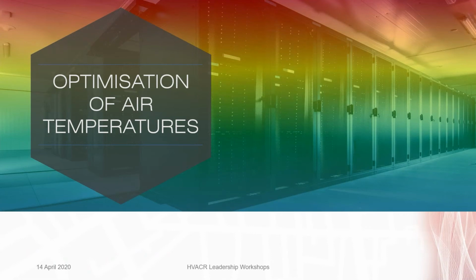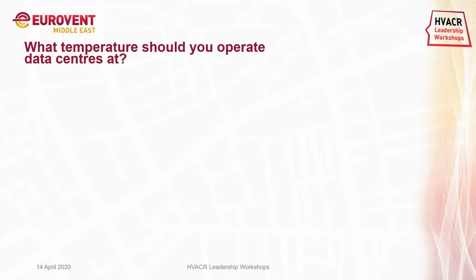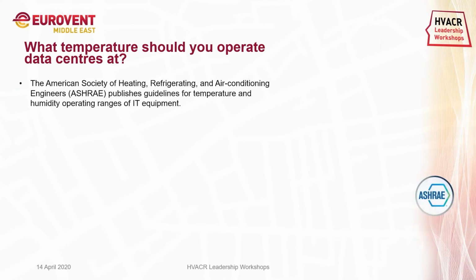Now, getting into more technical optimization of air temperatures, how we can optimize the air temperatures and increase the efficiency of a system. Now, what temperature should you operate data centers at? That's the main question. Which temperature do you want to design a data center cooling unit for? So we have some guidelines given by ASHRAE, the American Society of Heating, Refrigeration and Air Conditioning Engineers. They publish guidelines for temperature and humidity operating ranges of IT equipment. That is in the document ASHRAE TC 9.9, which covers data center power equipment thermal guidelines and best practices.